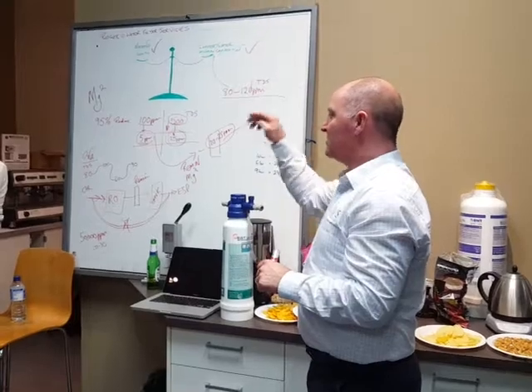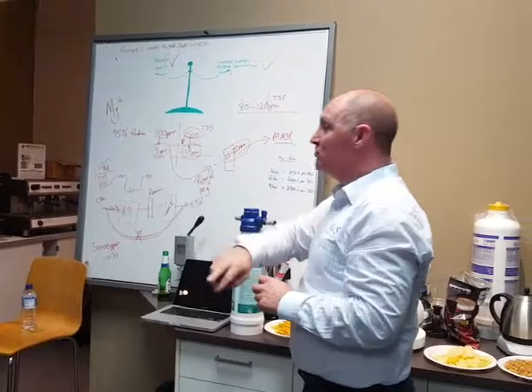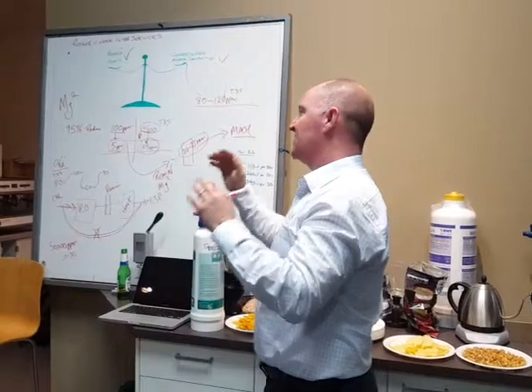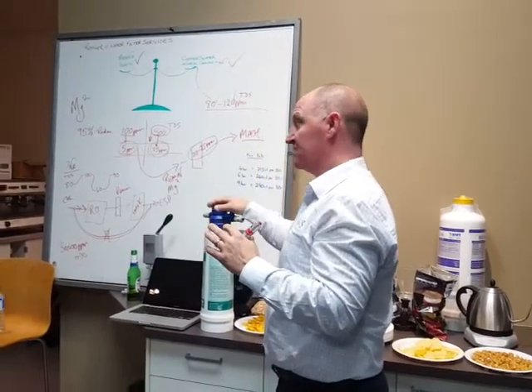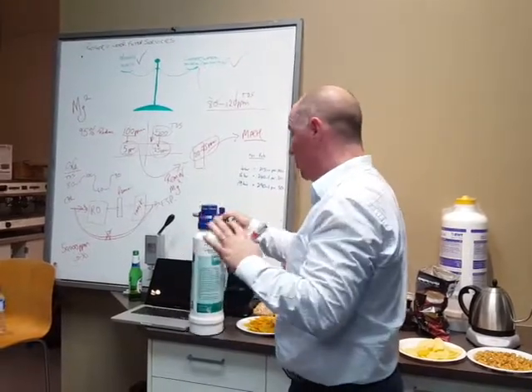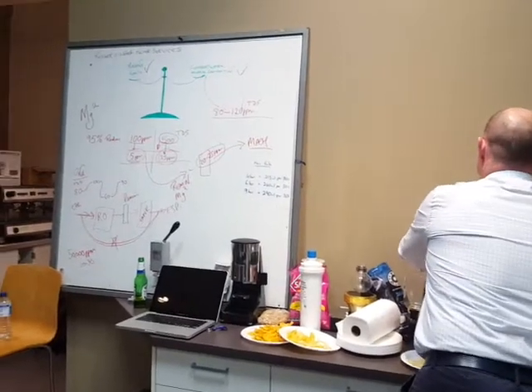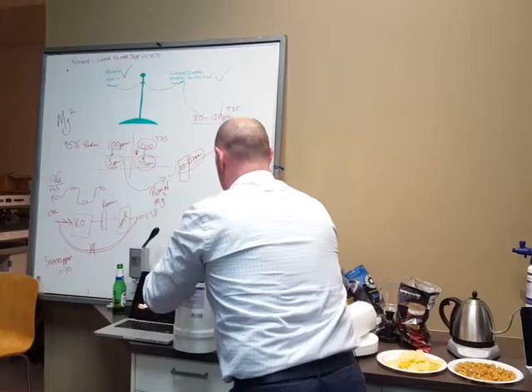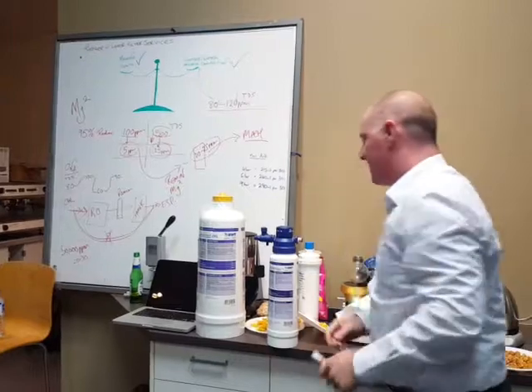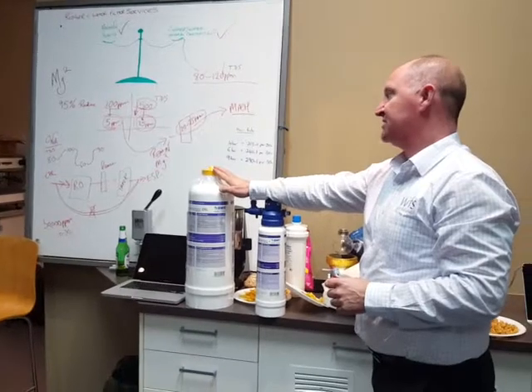So really, when we look at it, chlorides are a big issue. They're the ones that create corrosion. So if you're not 100% committed to investing all the money that's required for a reverse osmosis system, there really is only one filter cartridge in the world right now that is capable of doing it. And this is our second choice. So if you want to see how you go and put a filter cartridge in, this is your best option from a filter cartridge perspective.